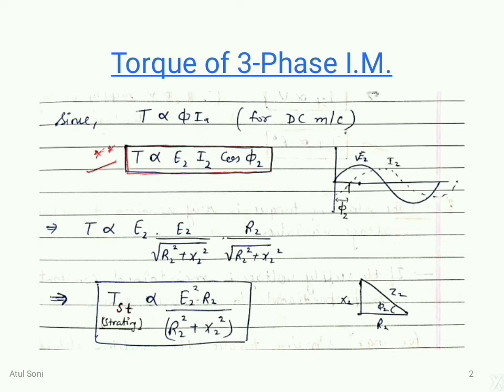From this derivation we get the starting torque equation: starting torque is directly proportional to E2² · R2 / (R2² + X2²). The starting torque requirement depends on the type of load — if it is a high-inertia load, the starting torque requirement is greater than the rated load torque.